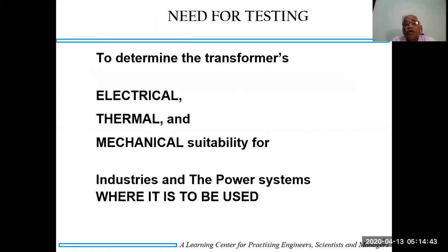Now, to determine the transformer's electrical, thermal and mechanical suitability. Electrically, that is the primary voltage, secondary voltage and the load current. Thermally, how much is the temperature rising, whether the transformer oil is sufficient to cool, or the body is sufficient, or the systems provided for cooling, ONAN or any forced cooling or whatever it may be, are thermally suitable so that the transformer temperature is not increasing beyond the design level.